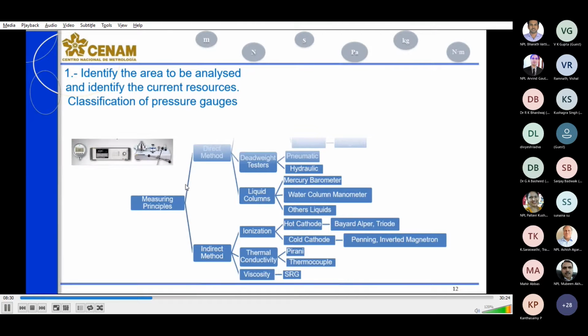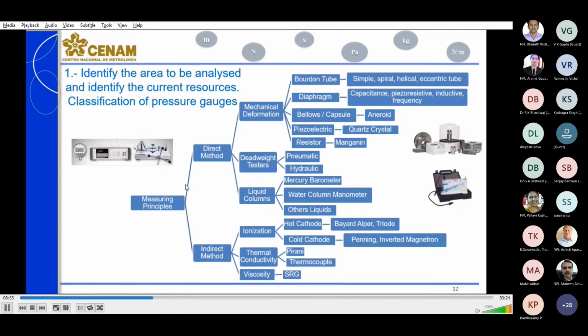The second part in identifying the area to be analyzed and identifying the current sources is to classify the pressure gauges that we are going to use as standards and to be calibrated or measured. And there are many different pressure measurements. You certainly have seen this graph and these instruments for pressure classification. We have direct method and indirect method. In the direct method, you can use mechanical deformation, dead weight testers, liquid column, and the indirect method is mainly used for vacuum. So we have ionization gauges, thermal conductivity gauges, and viscosity gauges. The type of instruments are there.